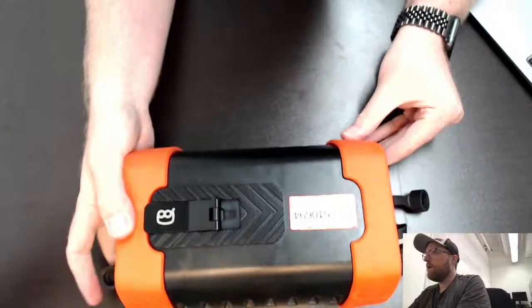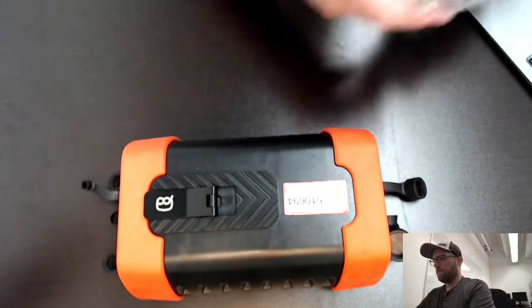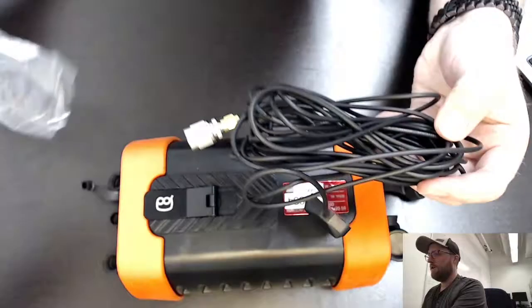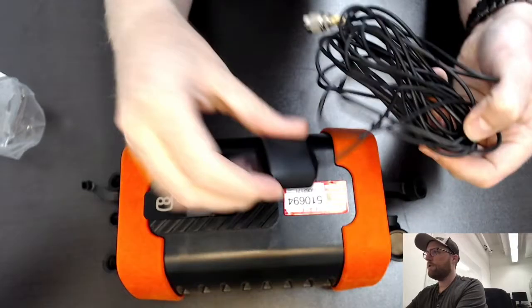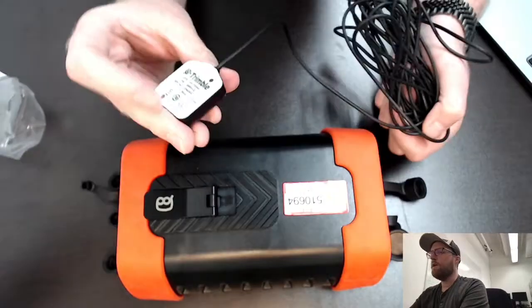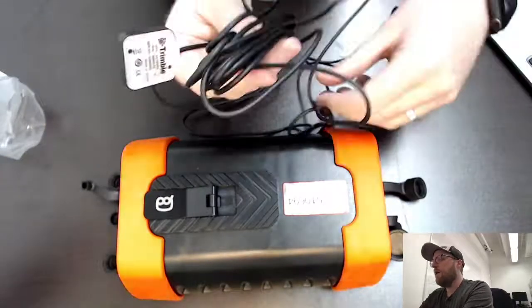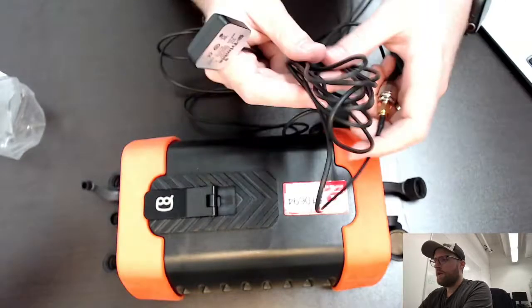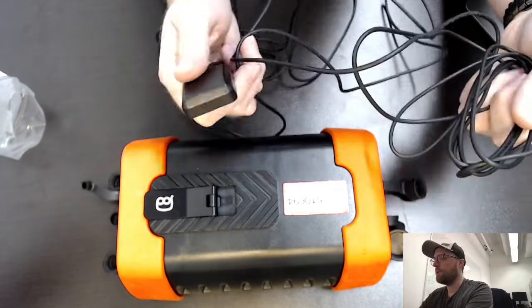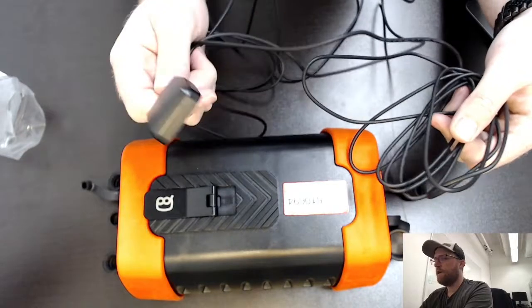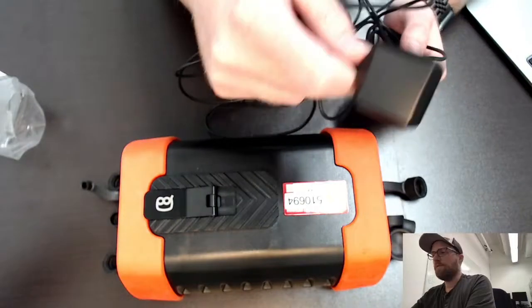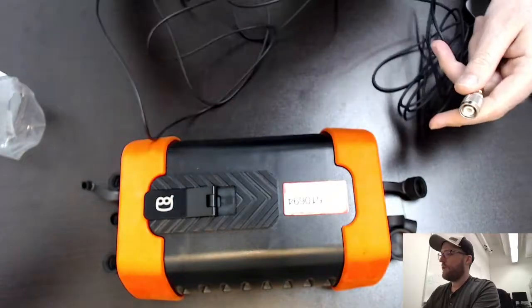So that's the device itself. Let's go through some of the accessories that came with it. So this first one, this is a Trimble GPS antenna. It's a pretty small magnetic mount. I don't have anything magnetic in this picture, but it comes with a pretty long cable. For us, we use this just for testing. At actual field sites, we have a more robust outdoor antenna that will connect. But this is good enough to test. And surprisingly, I get enough GPS signal in this basement room to get this thing going.